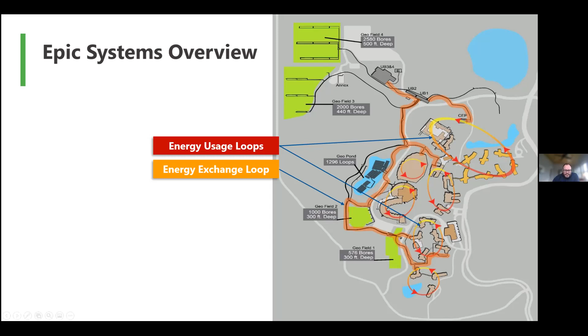Some specifics on the scale of the system and piping: this is 6,100 geothermal wells. The first field was drilled relatively shallowly; subsequent fields were to 500-foot depth, which equates to about 627 miles of vertical piping, for those who want to be impressed by the amount of plastic deployed here. The pond and quarry are quite large systems as well, 27 acres of system there, and the overall capacity is 27,000 tons of cooling and heating.